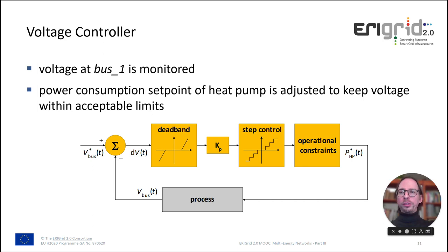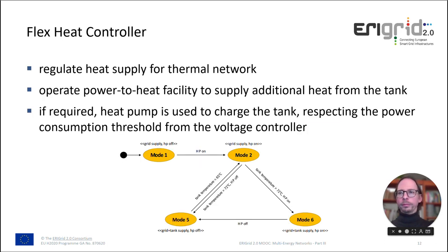The voltage controller monitors the voltage at bus 1 and calculates power consumption setpoints to adjust the voltage within accepted limits. The controller implements a step controller and sends its output to the flex-heat controller. The flex-heat controller then regulates the heat supply for the thermal network, and whenever required, the heat pump is used to charge the tank, always respecting the power consumption threshold from the voltage controller.